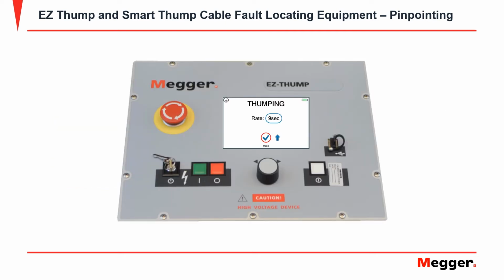After the desired voltage is selected, you'll come to a screen. That way you select how rapidly or how slow the discharge will occur, depending on the voltage setup. After the time is selected, you'll come to the screen to push green HV on. Once the green button is selected and pushed, then you'll begin the thumping process.